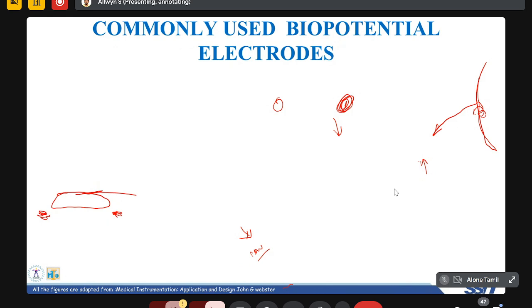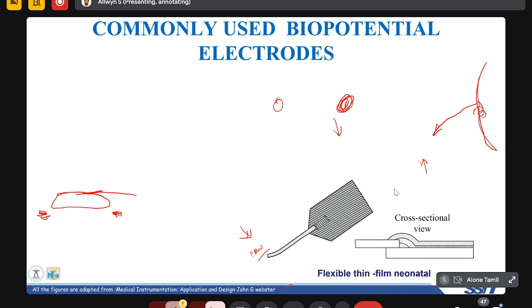And another one is carbon-filled silicone rubber. This is usually used in newborn babies, where you cannot simply stick other electrodes like a foam pad electrode, because their skin is very sensitive and if we try to remove those the skin may peel off. So usually they won't use this foam tape. Instead they use this carbon-filled silicone rubber and also flexible thin film metal. These are used for neonatal ECG applications.